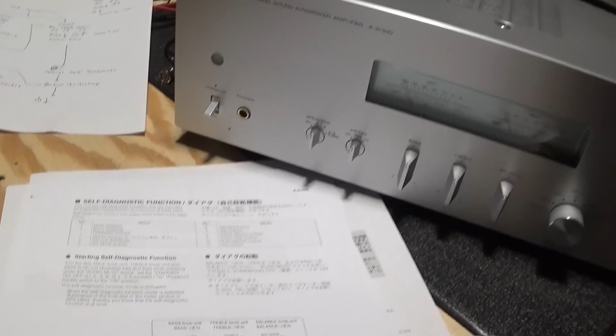But I'm going to test the theory, I'm going to see if that's actually what happened. So the feature of the Furman that I believe caused the issue is the fact that when the Furman loses power, and we lost power during this process several times, of course it turns off. Whenever it turns on, it doesn't just immediately provide 120 volts to the equipment. It ramps the voltage up slowly.